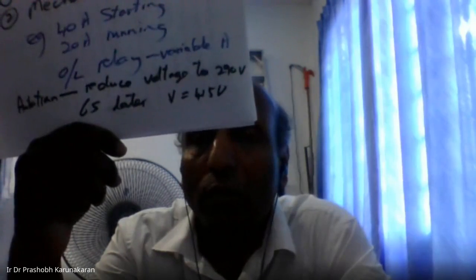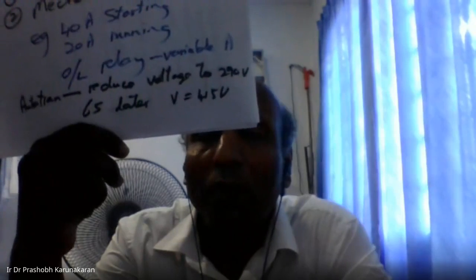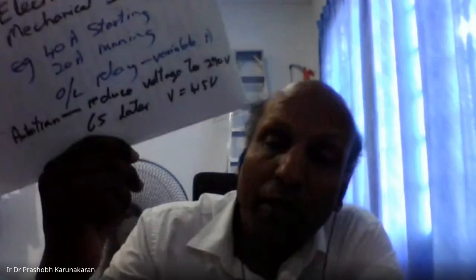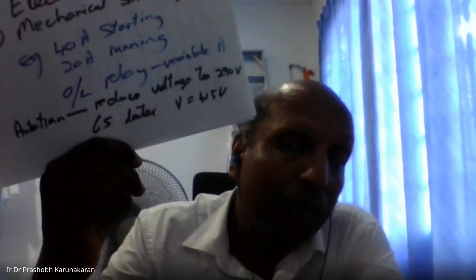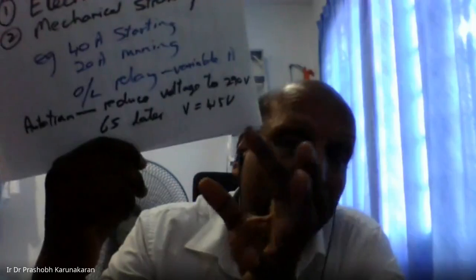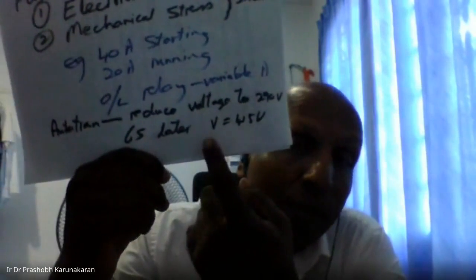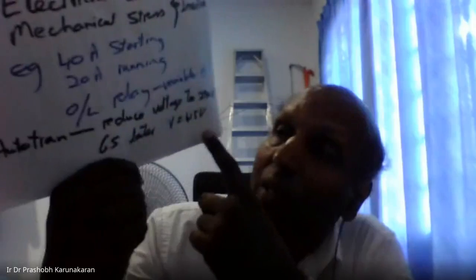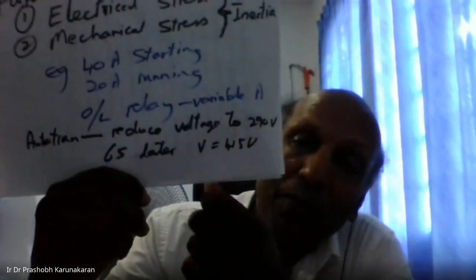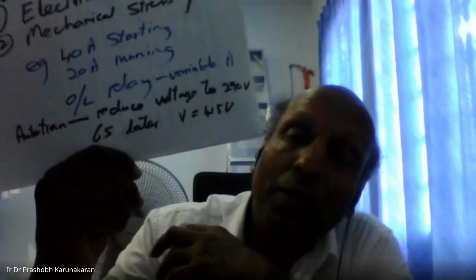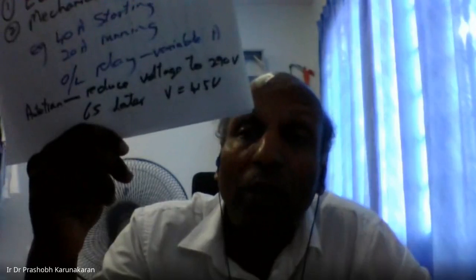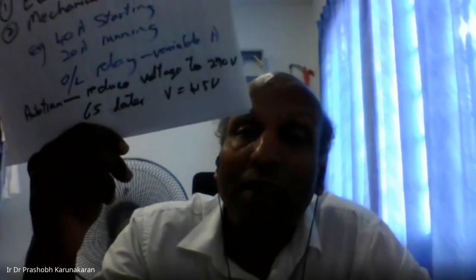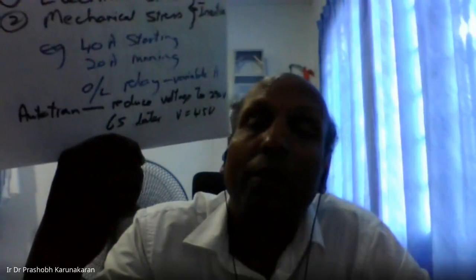So you reduce the voltage. If 415 volts goes in from the beginning, you still take in a lot of amp, double the amp. So the power, which is the one that can kill the wire, is reduced by half, because 290 is about half. The power going into the wire, which will cause the coil wires in the stator of the motor to burn, is the whole power. The power is the one that makes it hot. So the power is reduced by half. That's why you can reduce electrical stress and mechanical stress.